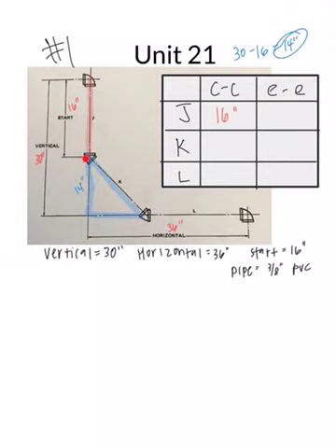And notice that you have two 45s and you have a right triangle, which means that both of the sides of your triangle are going to be the same. So this measurement's 14 inches. And so now to find pipe K, we can either do Pythagorean's theorem or there's the shortcut: 14 multiplied by the 45 constant, which is 1.414.